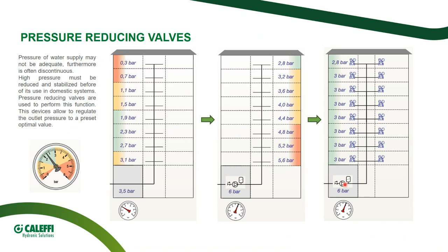So how can we do it? Okay, let's suppose the situation from before. I am entering the building with 3.5 bar, but the highest stories are not correctly supplied. I am missing water pressure. So the most common idea is, okay, let's install a booster group in order to ensure at least 2.8 bar to the highest floor. Then I might end up in the situation we just saw before, with the lower stories subjected to too high pressure. So the optimal regulation is, okay, let's keep the booster group, but let's equip every single story or apartment, depending on the nature of the building, with a pressure controlling device.